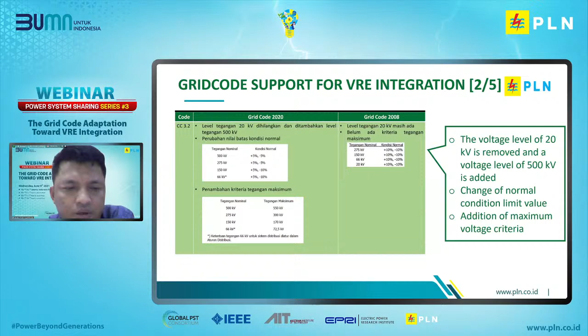We also add maximum voltage criteria. For example, for 500 kV, the maximum voltage is 550 kV, meanwhile for 275 kV it should be no more than 300 kV, and so on.